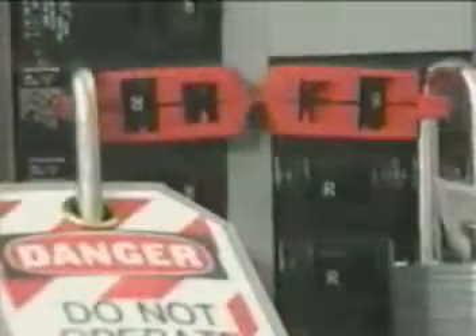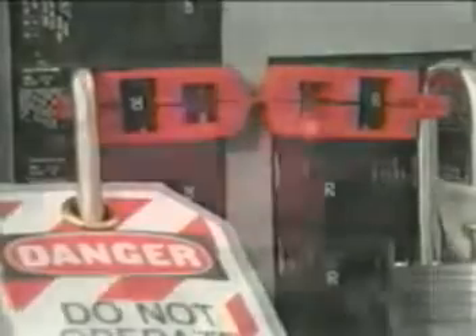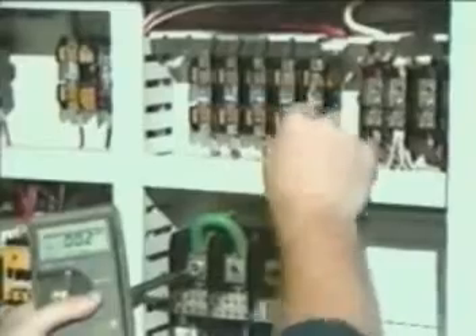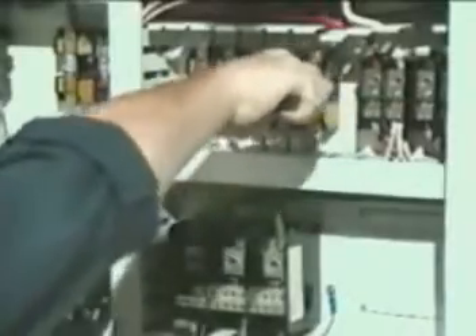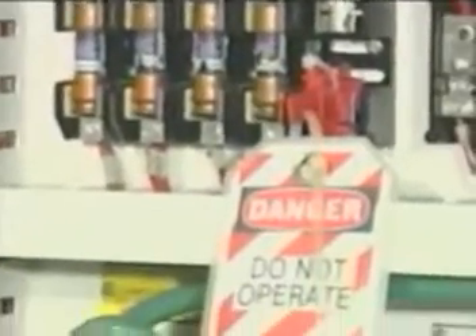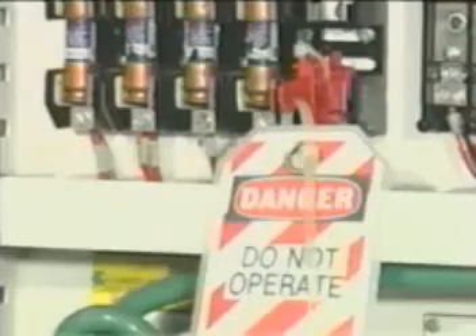For circuit breakers, place a circuit breaker lockout device over the breaker switch in the off position. Secure the device onto the breaker, then attach your lock and tag through the hole. You can even lock out multi-pole breakers with various devices. To lock out fuses, first verify the circuit is de-energized. Then remove the fuse with an approved fuse puller. Place the fuse lockout in the fuse holder and attach a tie wrap and tag.